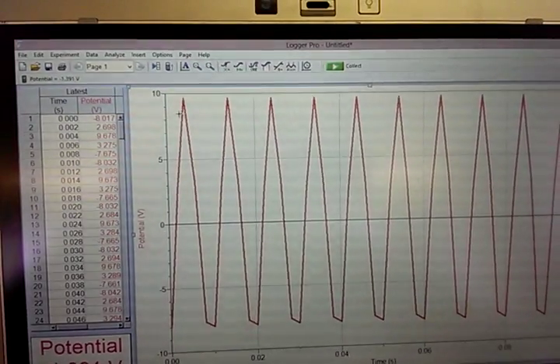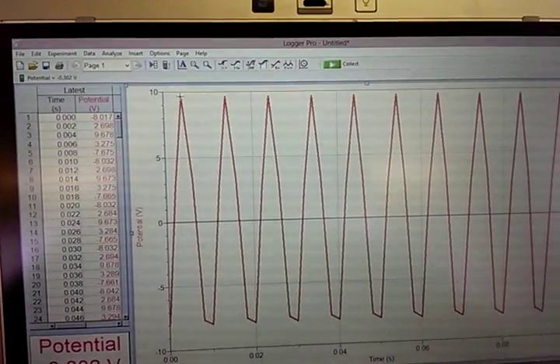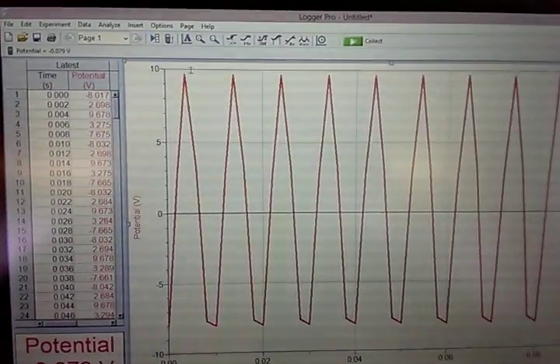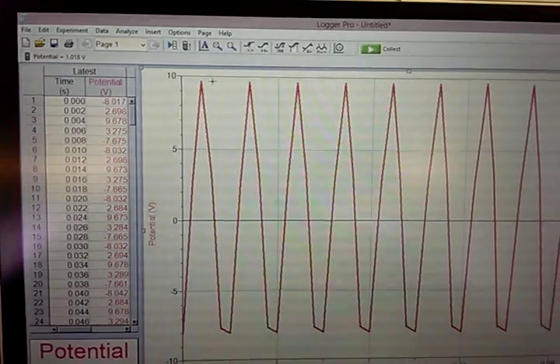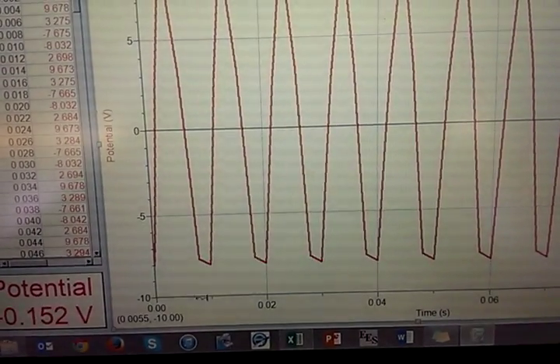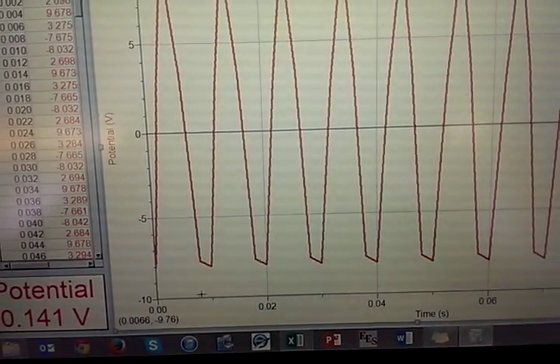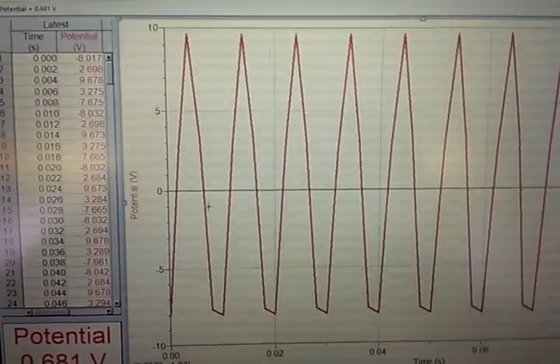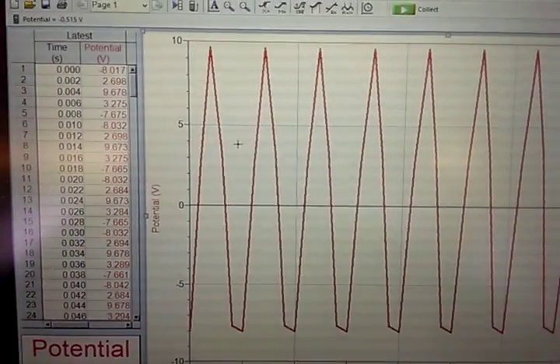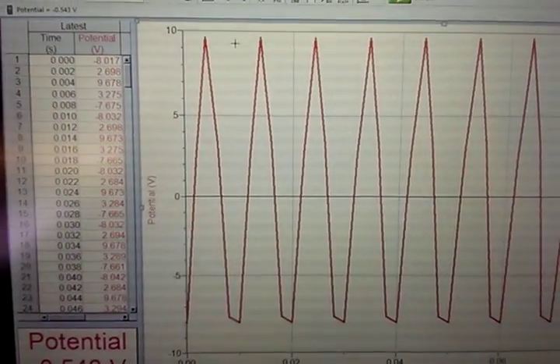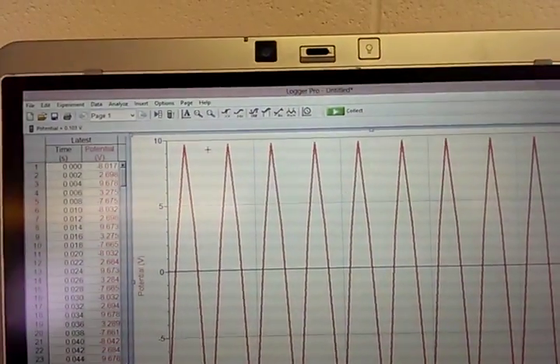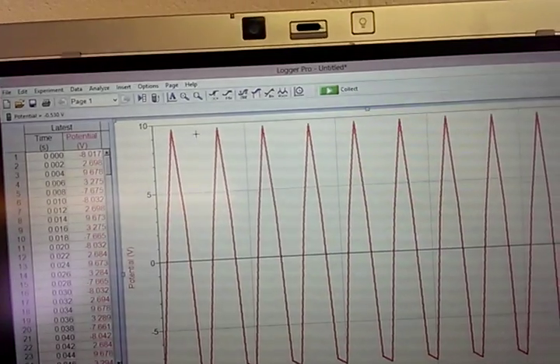In order to be able to see the little bit that would clip up here, just due to the fact that you're looking at a very small time window right here, as displayed by moving the cursor back and forth. According to this, it looks like it's not even 0.01 seconds, so you're going to need to make sure that you can demonstrate that, which is saturation.